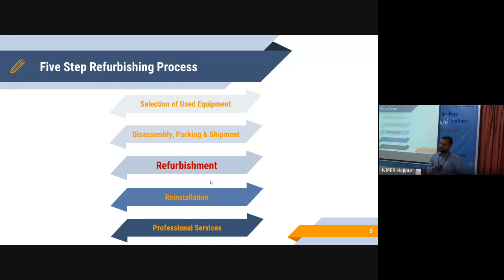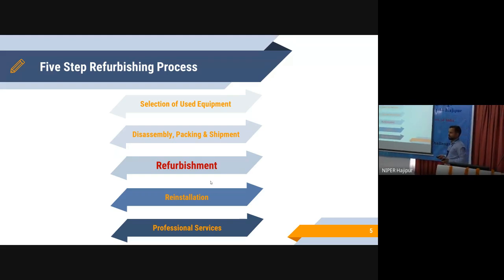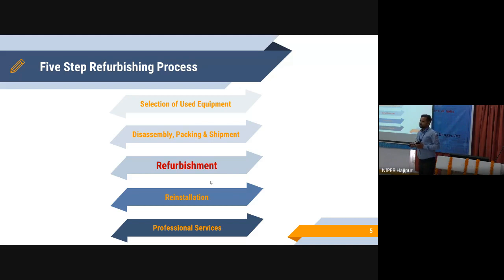When the shipped medical device reaches the site where refurbishment has to be done, the first step is cleaning. The party has to clean or disinfect the medical device before performing the refurbishment. Then they have to do whatever electrical and mechanical refurbishment is required, including some polishing, painting, cosmetic touch-ups, system upgradability and software upgrades, and in the last step they have to check for the optimal system performance of the refurbished medical device. Now the fourth step is the reinstallation.